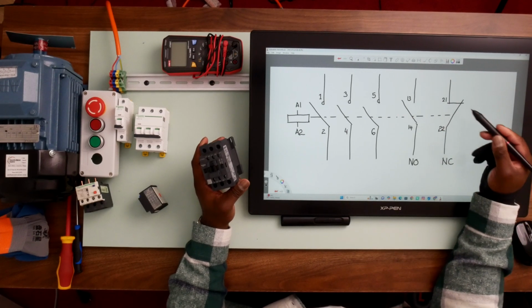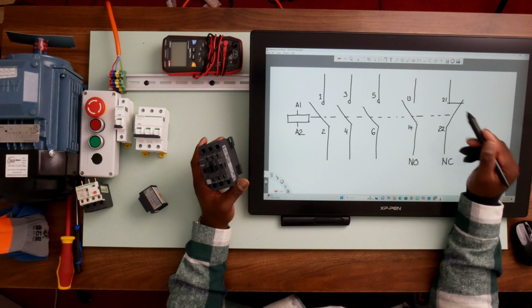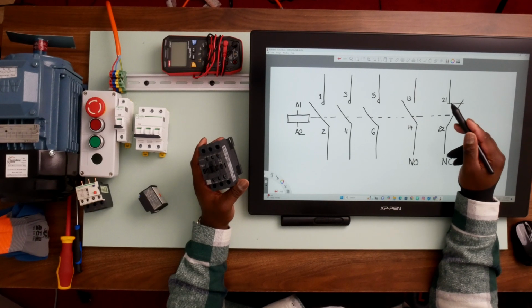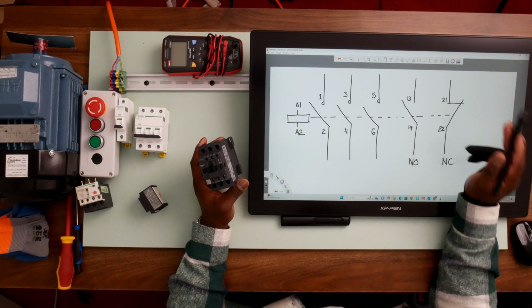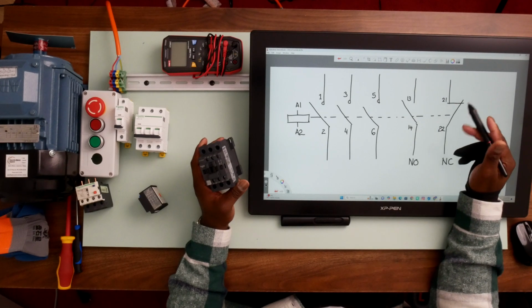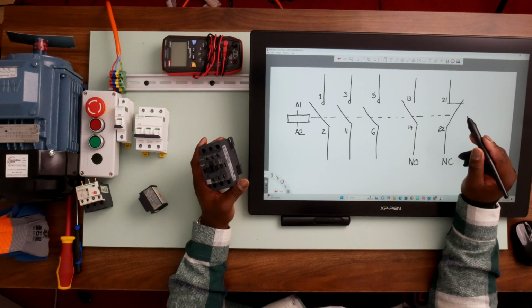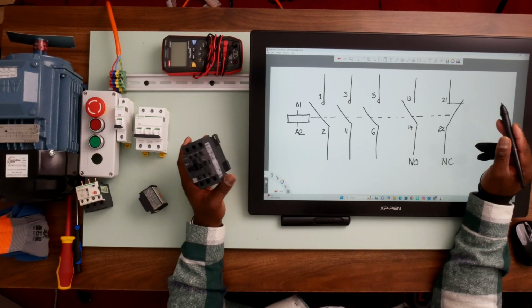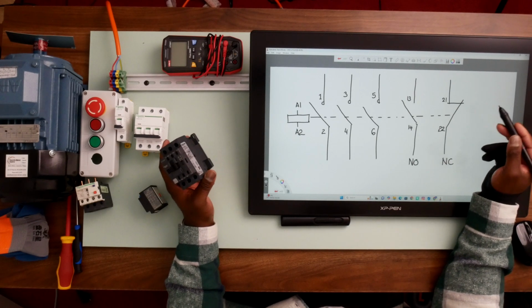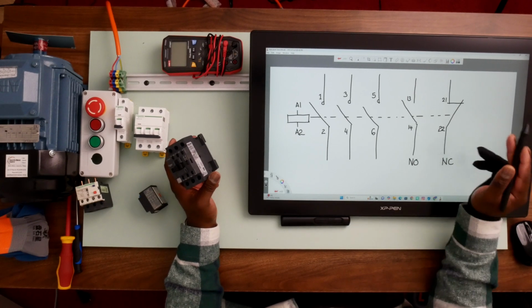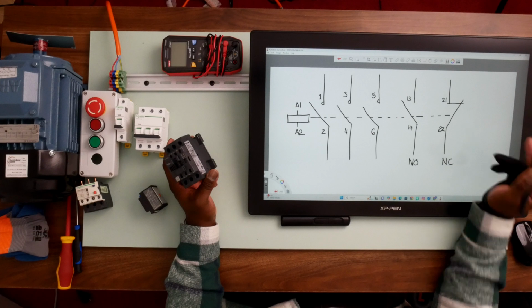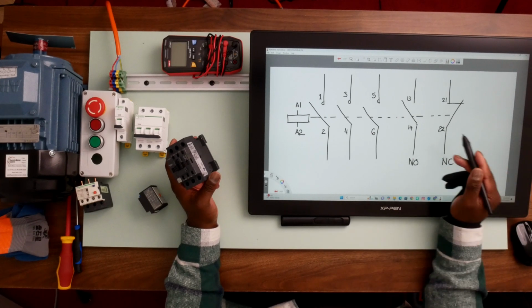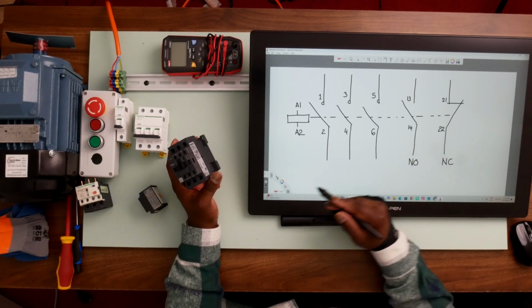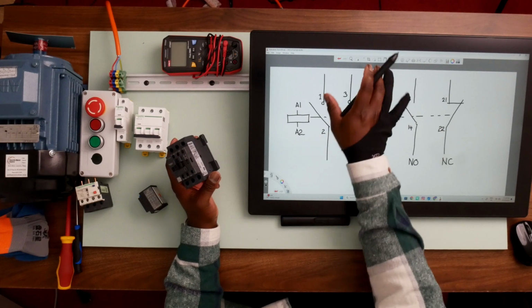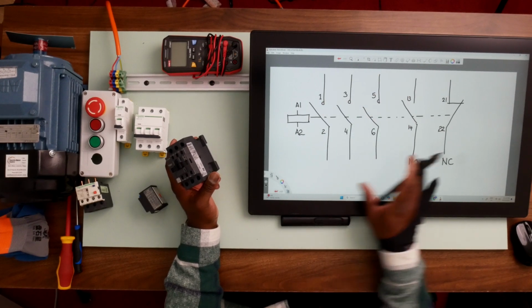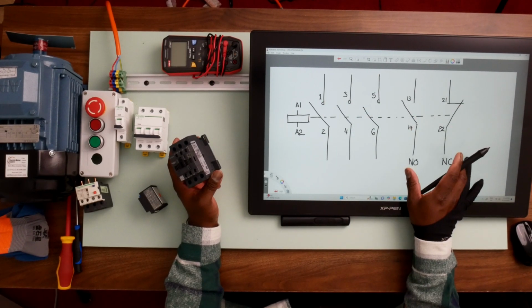And on normally closed contacts, as long as the least significant numbers are 1 and 2, that tells you that it's a normally closed contact. So normally closed contacts always end in 1 and 2. They could be 1, 2, 21, 22, or 41, 42, as long as the least significant numbers are 1 and 2. So this is the symbol for a contactor. This part belongs to the power circuit and this part belongs to the control circuit.